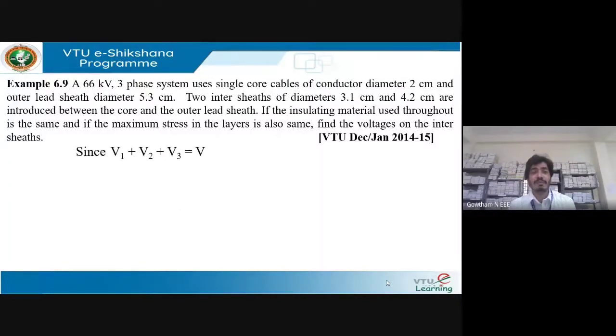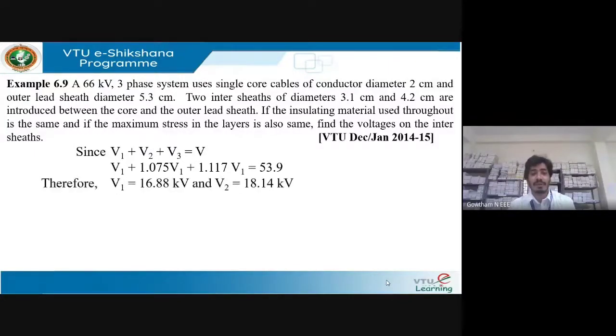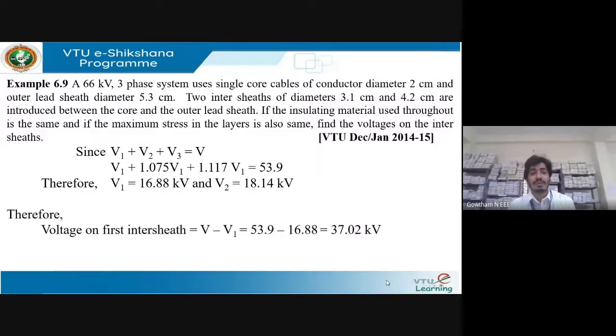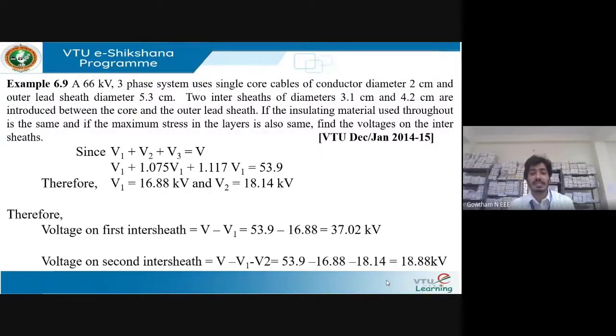Since V1 + V2 + V3 = V, substituting the expressions for V2 and V3 and the known V, we find V1 = 16.88 kV and V2 = 18.14 kV. Voltage on the first intersheath = V − V1 = 53.9 − 16.88 = 37.02 kV. Voltage on the second intersheath = V − V1 − V2 = 18.88 kV.